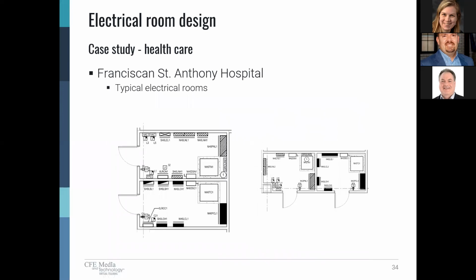And then finally, I wanted to look at our typical electrical closets that we had in every area of the building on every floor. In this particular example, we separated out the essential system from the normal distribution. We had them in two separate electrical closets in every area. You can see as these rooms are laid out, we've got adequate working clearances in front of the gear. And in these rooms, you can see that we've got panel boards that are directly across from panel boards. So we had to take into consideration live working parts on both ends, as dictated by NEC 110.26a.